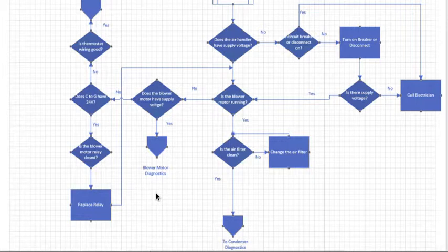If everything's fine in the air handler, you can move on because the problem's not the air handler. But if you come across any problems in the air handler, you have to repair those before you can move on to the rest of the diagnostic. And just because you find a problem in the air handler does not mean you should stop there. You fix it, but then you still have to do the rest of your diagnostics to make sure there's not more problems.